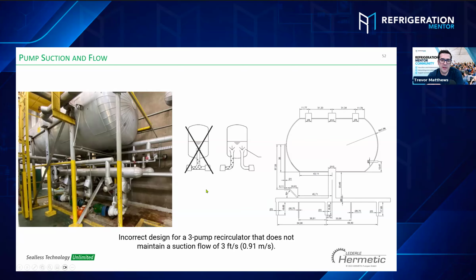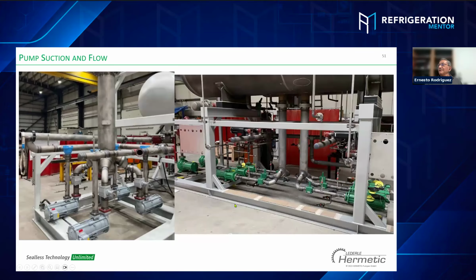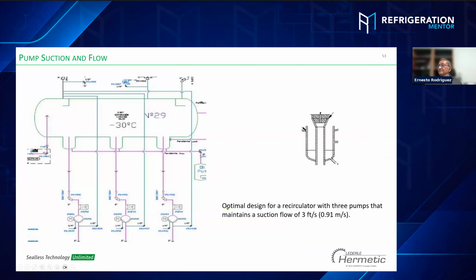So in this example, the first one that got an X on it is just one outlet of the vessel feeding multiple pumps, even though it's piped evenly. Like this first one we're looking at, in the picture on the right-hand side, it comes down and then reaches that last pump. If all three pumps are working, that last pump might not even get any liquid. If you piped it down in a T and distributed it evenly, it's still not as good as having two outlets on the vessel. Yes, exactly. This is the reason for the rule. This is the correct way to install the pumps: the main leg and the three subsystems right here, for multiple pumps.